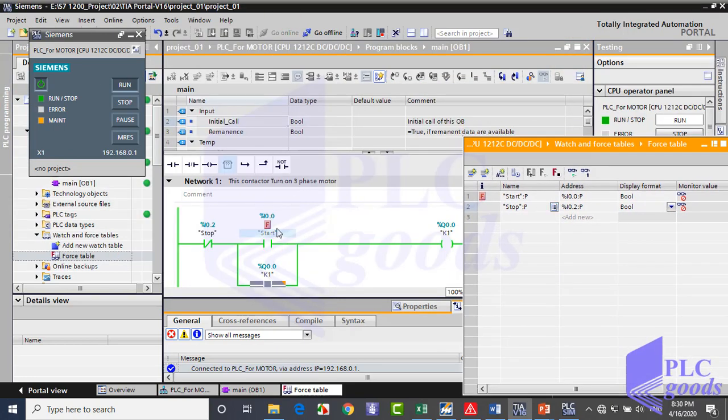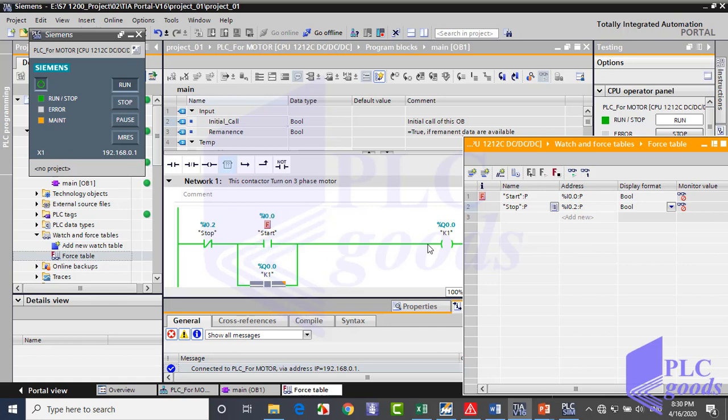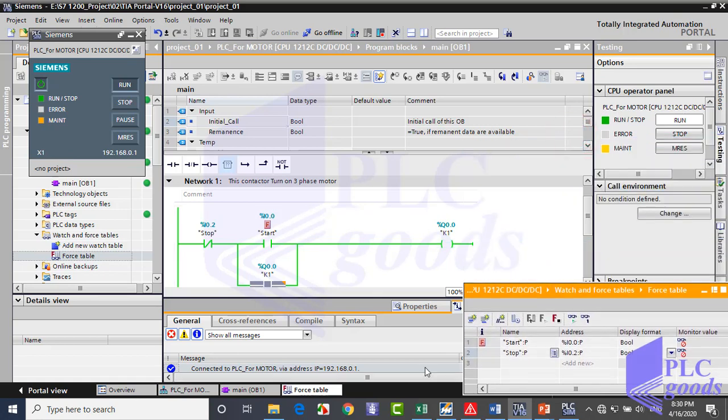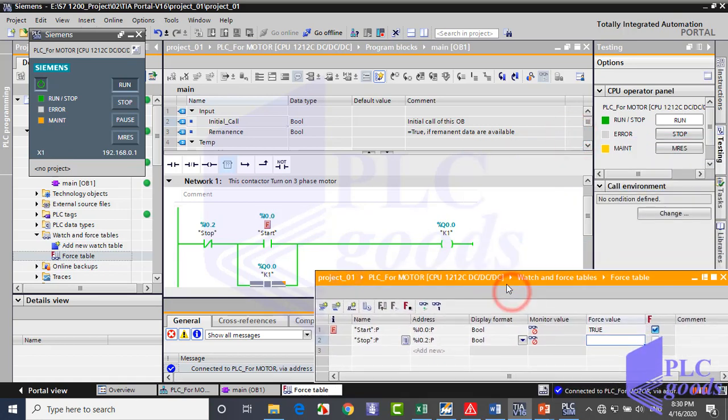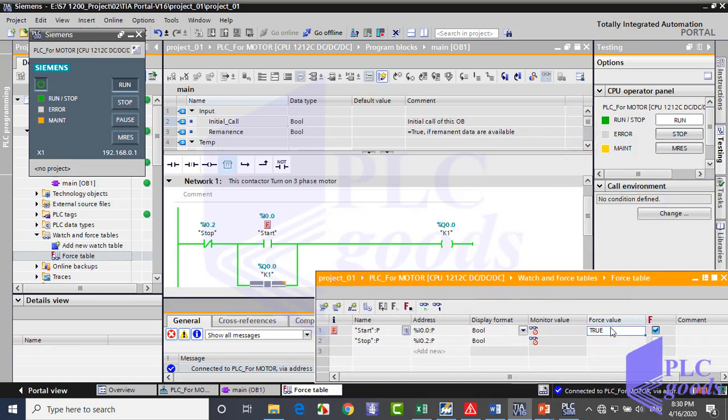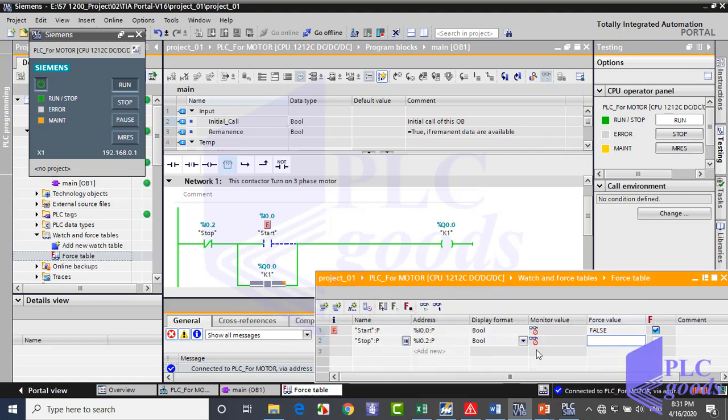As you see, a letter F is shown here because this contact with the address of the PLC input gets its value from the force table instead of its input. Also its color is changed to green from blue, and now passes virtual power to the output. Let me change it again. Well, let me have a better view. Now I'm going to give 0 value to the start contact. As you see, its color returns to blue and doesn't pass the virtual power. But our output is still on because of this branch.